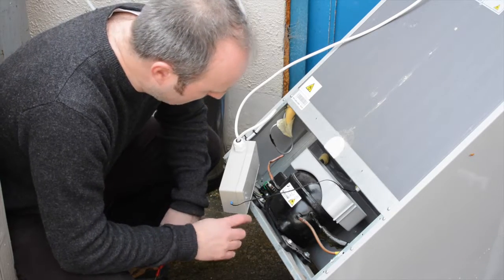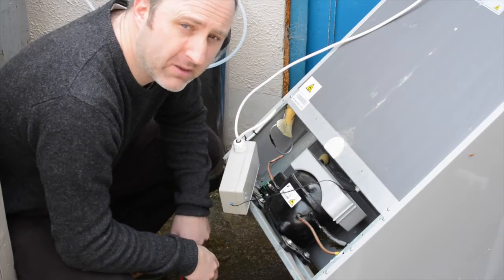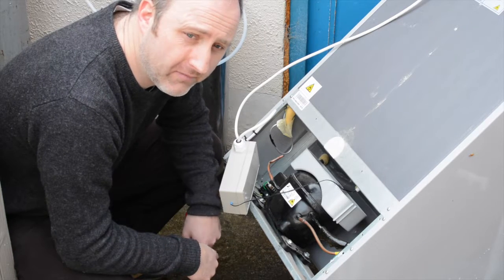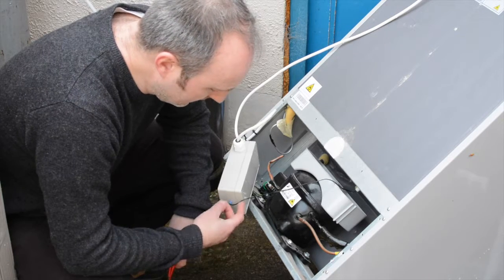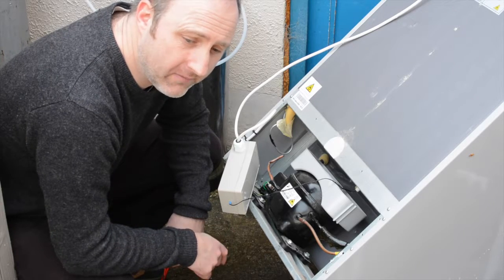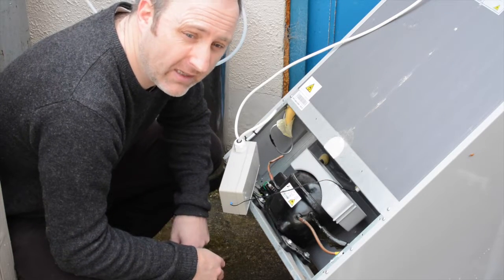What I'm going to do is put a wire up on the junction box up here to the top, and from this box here I'm going to run an electric power supply out of it for a heater which is actually going to go inside the fridge. I'm also going to run this thermometer cable from here but inside the fridge. At the moment I'm running it through the drainage plug which is okay but not a really good solution.